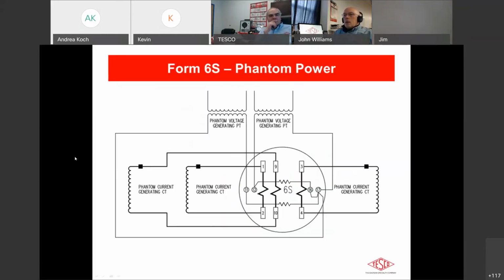Thanks for that. And again, in this case, we have the 2 potential transformers. Typically, as you can see, it's getting a bit repetitive in terms of the test board applications here. But realistically, it boils down to the number of elements in the meter dictating the number of phantom transformers needed to drive that meter. And then any of the phasor relationships between the voltages and the currents and between phases themselves can be handled with software.